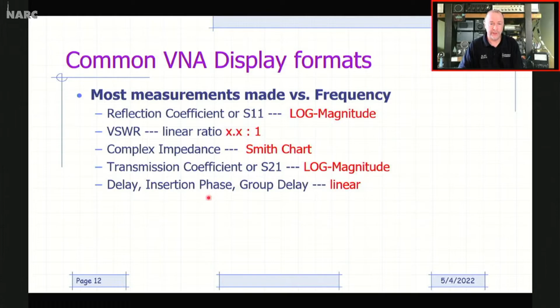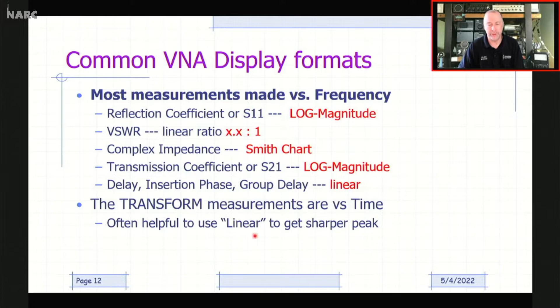As I mentioned, there's a transform measurement, which is typically a mathematical transform applied to the reflection properties, and that will result in giving you a measurement versus time instead of versus frequency. That can be converted into being able to look for things like distance to fault or length of a piece of coax, for example. It will typically use the reflection coefficient as the measurement, but it's helpful to change it from log mag to linear, because the plot will give you a sharper peak as opposed to a bit of a rounded peak in the result, a more precise measurement, just because you get a pointed peak typically by switching to linear. So with all that, that's the very basic understanding of what a VNA is.